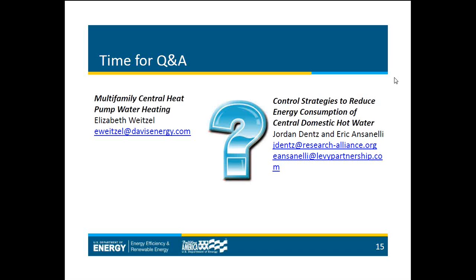I'll go through those first. The first one is, in the modeling, was the demand profile based on the measured data for the student village, or was it a standardized profile? At first, for the validation part of the modeling, we used profiles from monitored data. But when we went to the annual comparisons, we went to a standard draw profile that was informed by the ASHRAE service water heating guidelines.